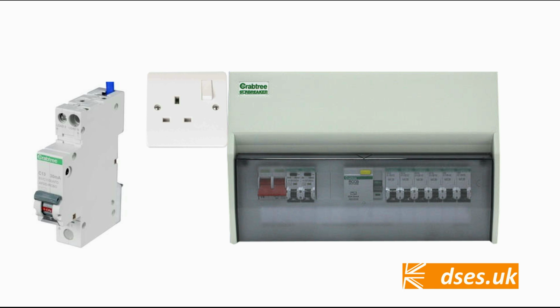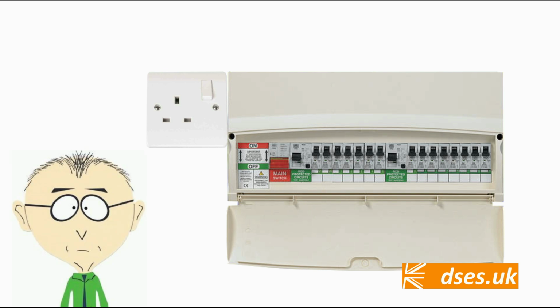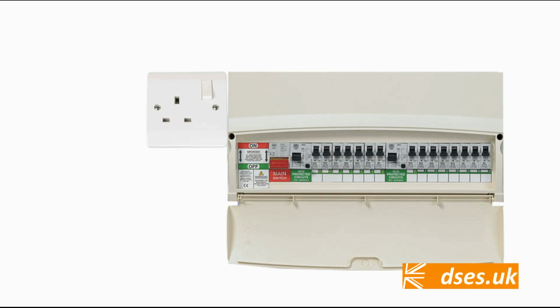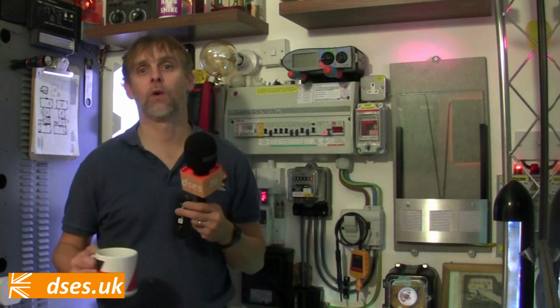But what if this were another brand of consumer unit such as MK? Okay. They were a popular choice for years, but MK left the consumer unit market quite recently, probably because they looked at the regs requiring SPDs, AFDDs and Type A RCDs and thought, to hell with the R&D on this. So I presume MK aren't going to be making AFDDs for what are now obsolete boards. So from 2022, if I have to install a new circuit and there is no supported AFDD for the existing board, we'll be looking at requiring a CU upgrade or a secondary enclosure containing the tech which is up to snuff. I guess that's okay. It's been the same for years where RCD protection has been required and you don't want anything to do with the existing electrics.